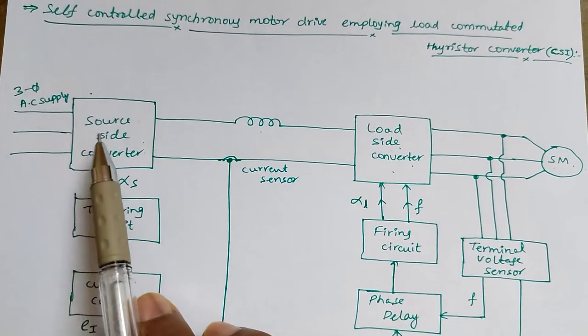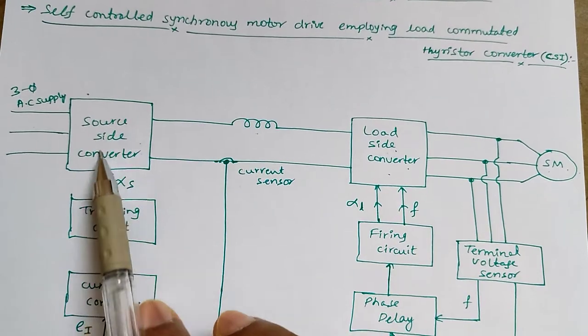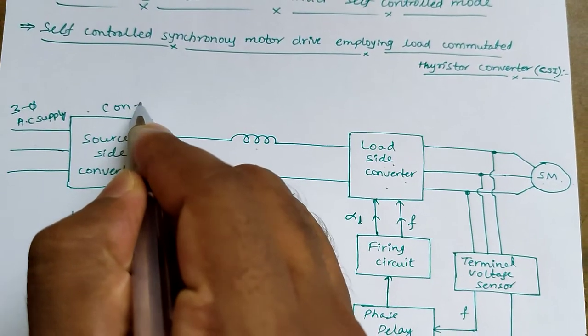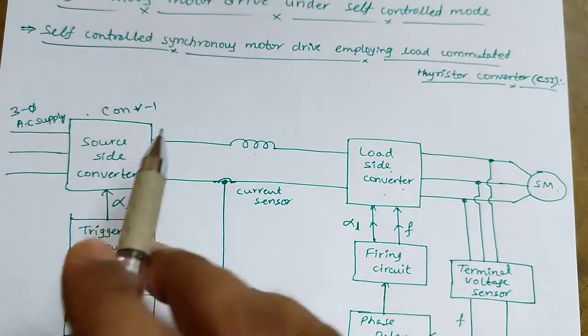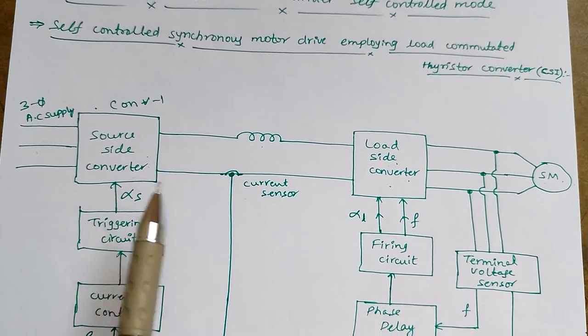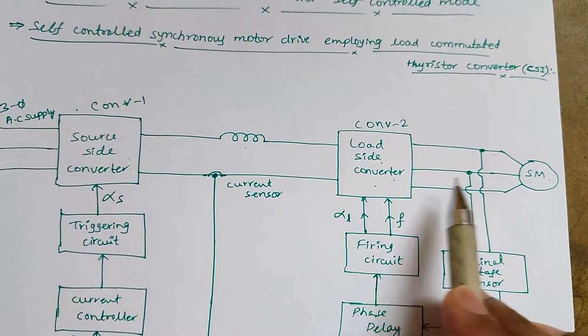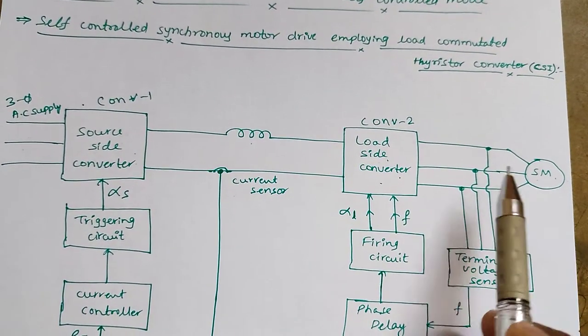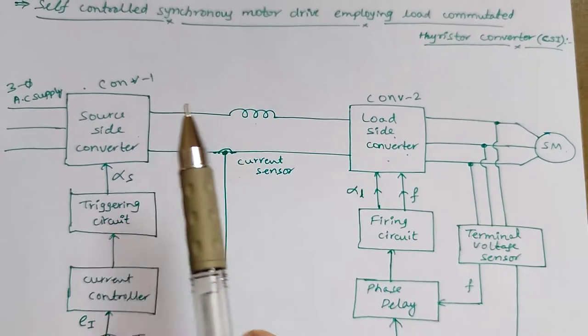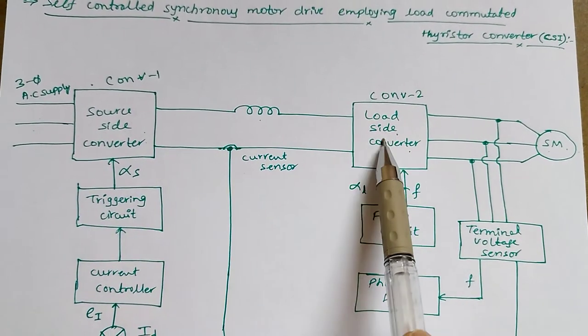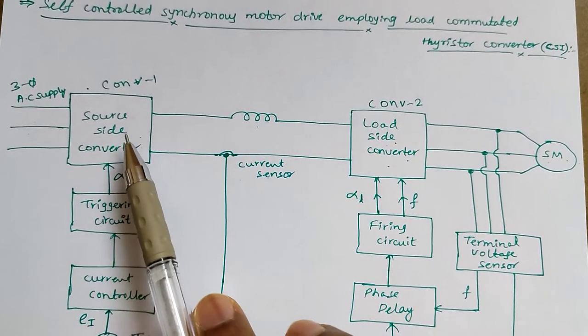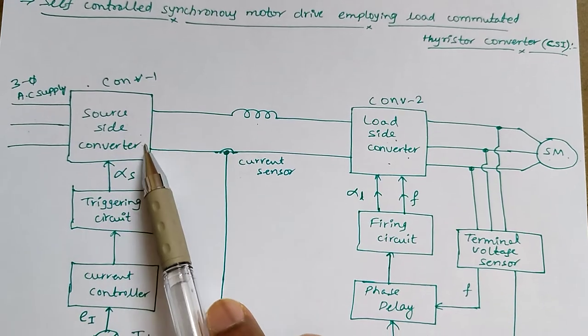A three-phase AC supply is connected to the rectifier, called the source side converter (Converter 1), because it is connected on the source side. Converter 2 is connected on the motor side or load side, so it is called the load side converter. Between the source side converter and load side converter, a DC link inductor is connected to remove the ripples in the output current of the source side converter.